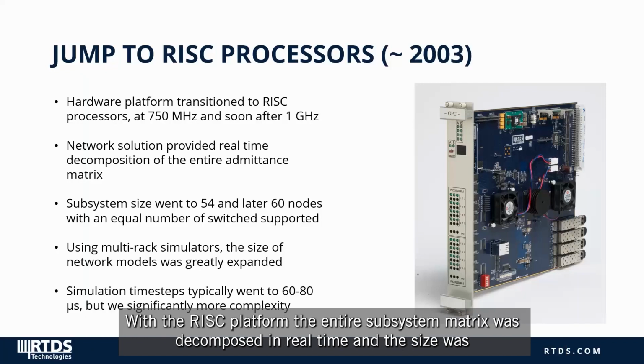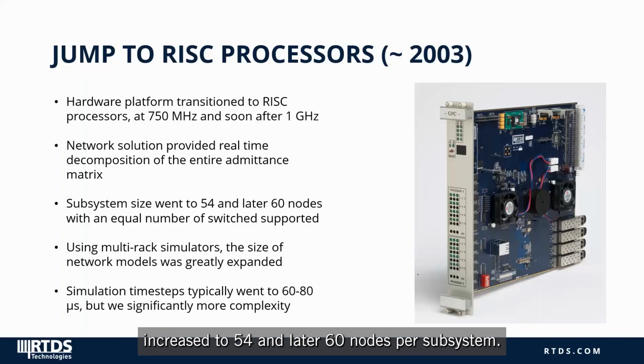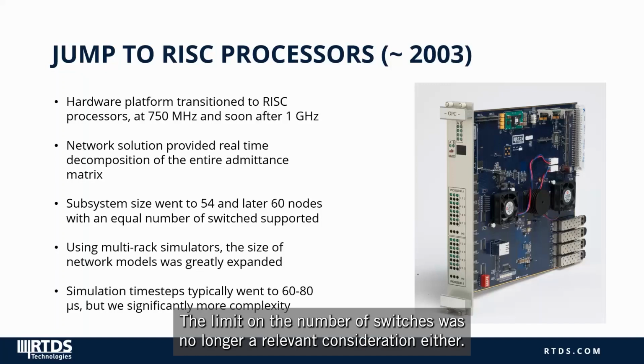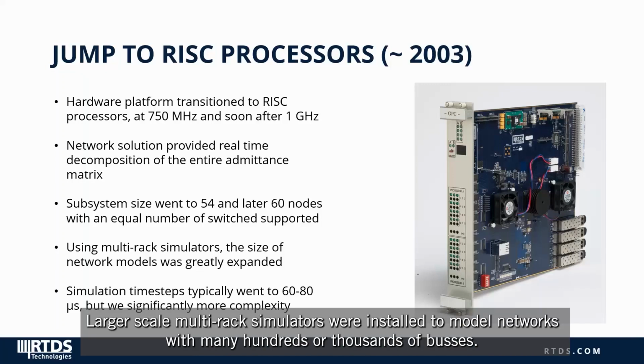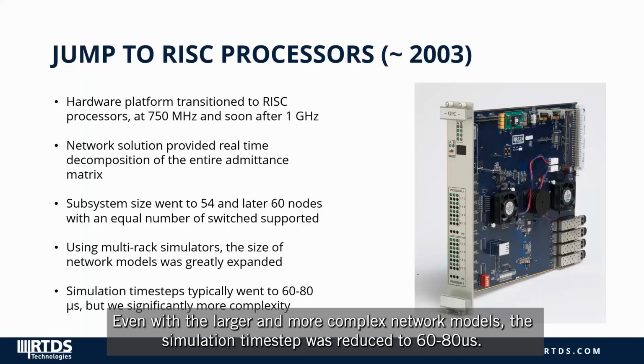With the RISC platform, the entire subsystem matrix was decomposed in real time, and the size was increased to 54 and later 60 nodes per subsystem. The limit on the number of switches was no longer a relevant consideration either. Larger scale multi-rack simulators were installed to model networks with many hundreds or thousands of buses. Even with the larger and more complex network models, the simulation time step was reduced to 60 to 80 microseconds.